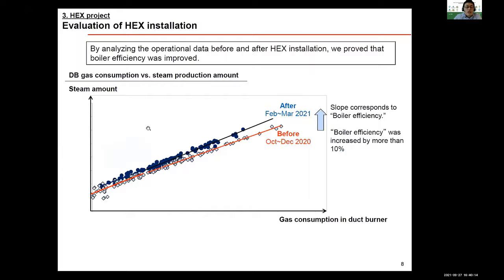Then the next slide shows a summary of the result. The X-axis represents gas consumption in the duct burner. The Y-axis represents steam production amount. This light blue rectangle shows hourly data before heat exchanger installation, and this dark blue circle shows the data after installation. In this graph, you can see the regression line has become steeper after installation. Technically speaking, the slope of the regression line corresponds to boiler efficiency. Therefore, in this graph, you can see boiler efficiency was increased by more than 10% after installation.